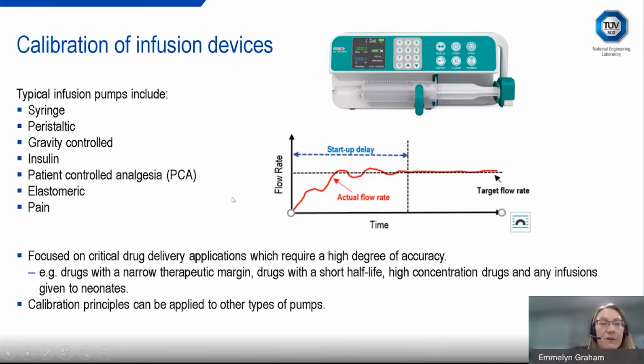So typical infusion pumps which are used, you have your syringe pumps, peristaltic, you can have gravity controlled, insulin pen pumps. There's a huge number. What we have focused on is critical applications which require a high degree of accuracy, and these may be used for drugs with a very narrow therapeutic margin, drugs with a short half-life, and any high concentration drugs or drugs which are given to very, very small children. But the calibration principles can be applied to any type of pump.